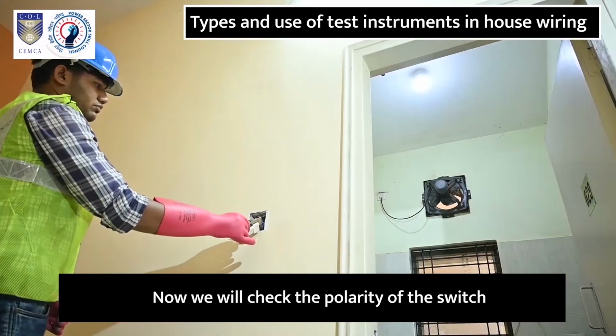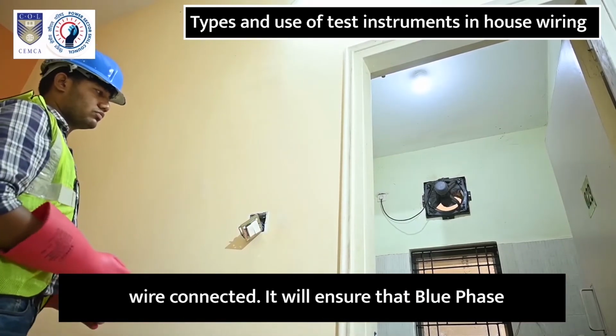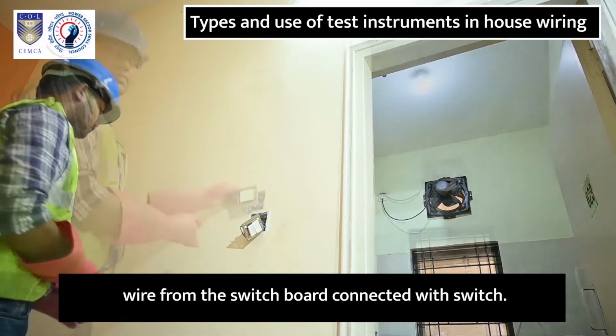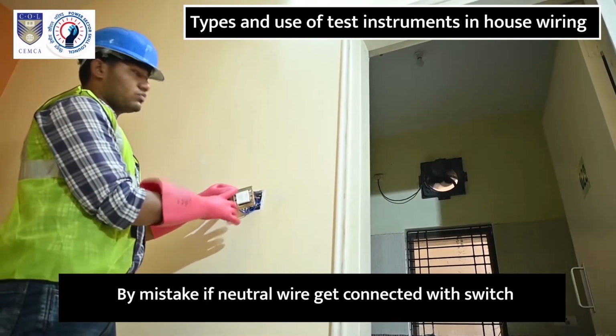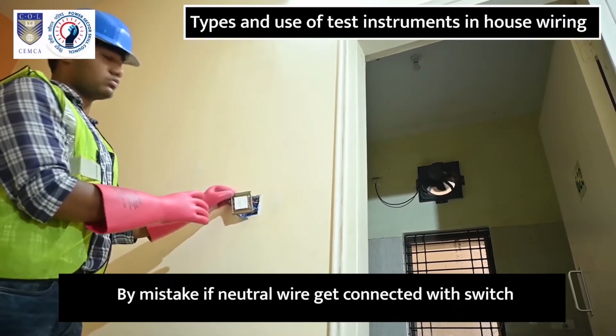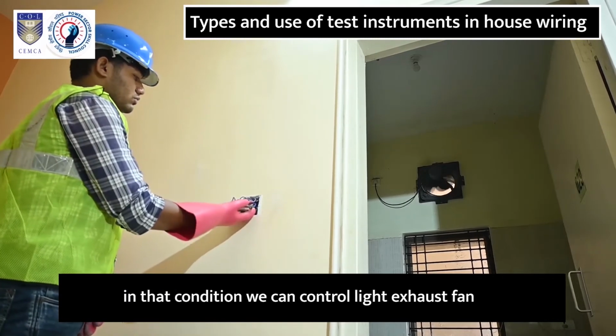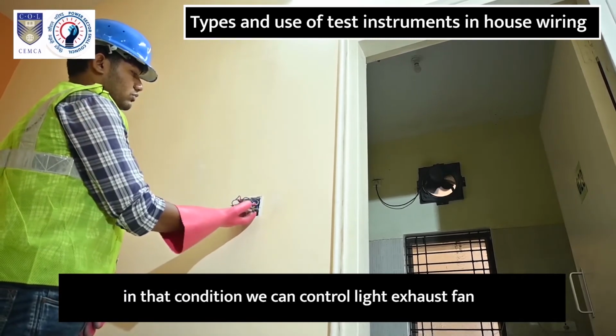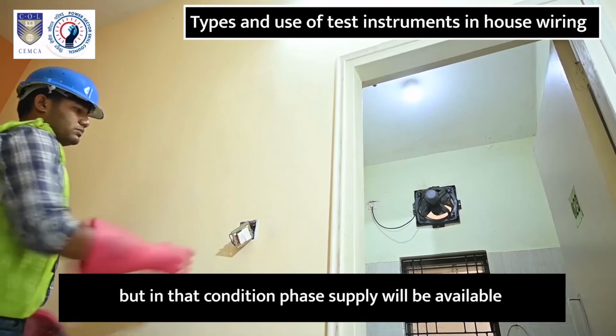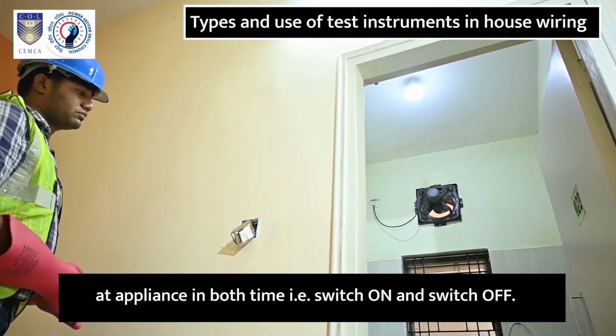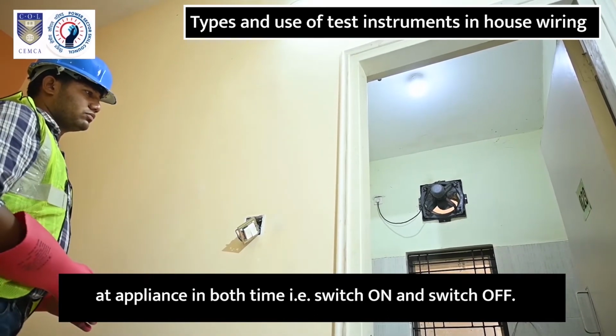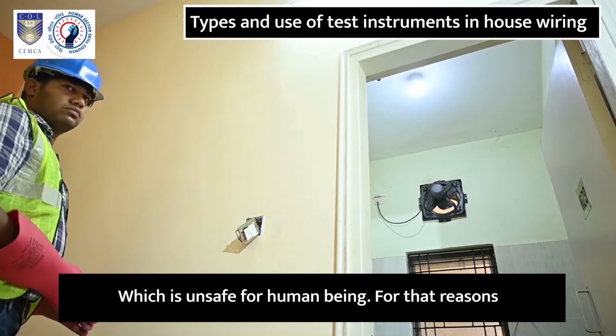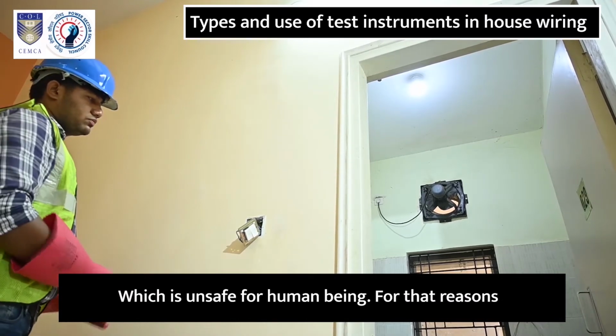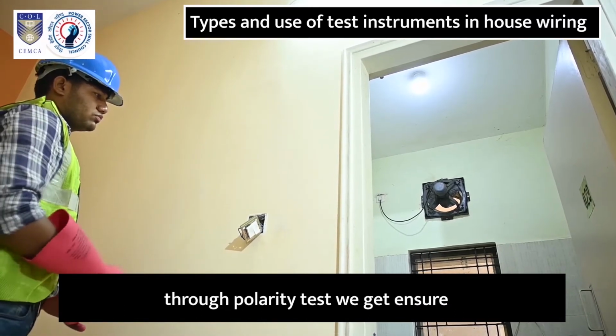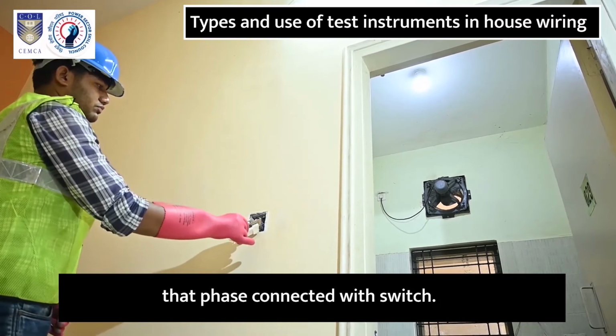Now we will check the polarity of the switch wire connected. It will ensure that blue phase wire from the switchboard is connected with the switch. By mistake, if neutral wire gets connected with the switch, in that condition we can still control the light and exhaust fan. But in that condition, phase supply will be available at the appliance both times, that is switch on and switch off, which is unsafe for human beings. For that reason, through polarity tests, we ensure that phase is connected with the switch.